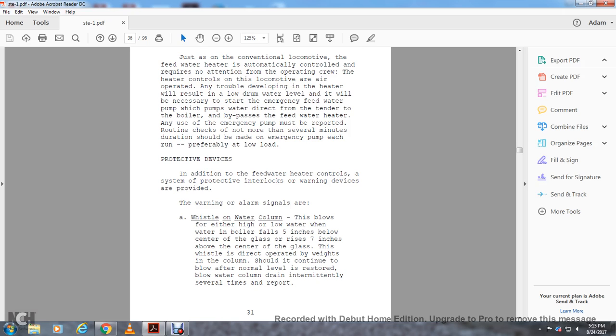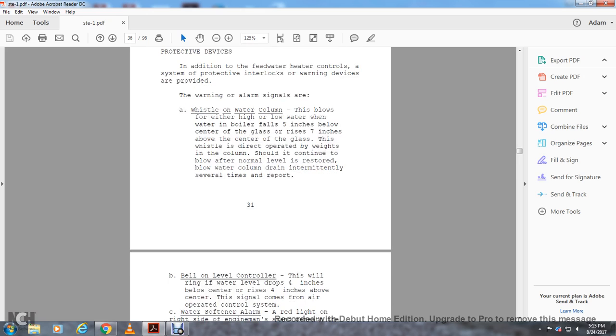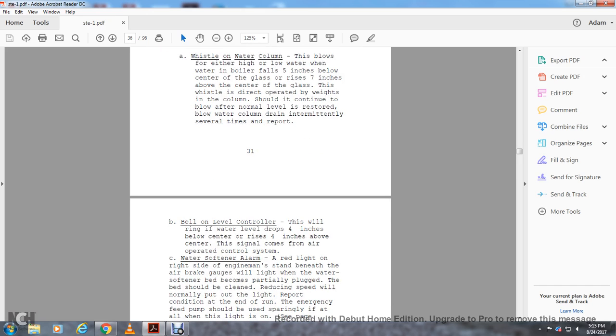Should it continue to blow after the normal level is restored, blow down the water column drain intermittently several times and report. Bell on the level controller. This will ring when the water level drops 4 inches below the center or rises 4 inches above the center of the glass. The signal comes from the air operated control system.